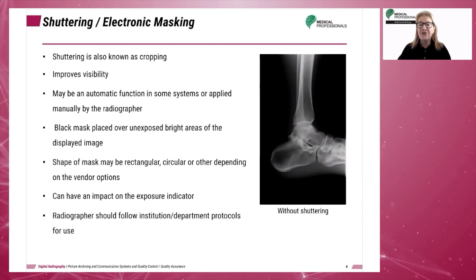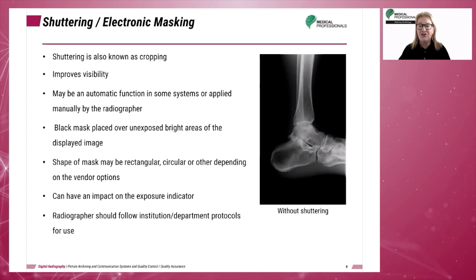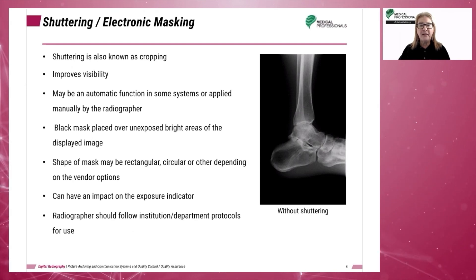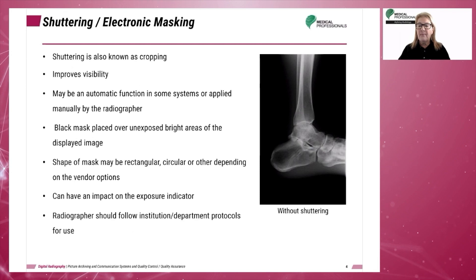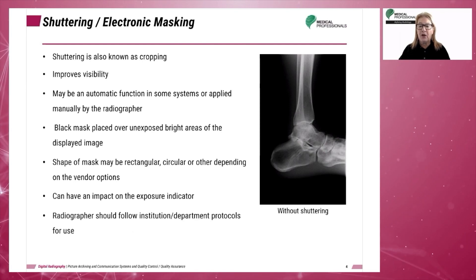Image shuttering allows the radiographer to place a black border or background around the original collimated edges of the image. The black border eliminates any white areas seen around a collimated image. Image shuttering is not to be used as a replacement for actual pre-exposure collimation or beam restriction. Proper collimation restricts the x-ray beam to the anatomy of interest, reduces patient dose, and increases contrast resolution by reducing the amount of scatter produced. Image shuttering simply makes the displayed image more aesthetically pleasing to the viewer, and institutional and departmental protocols should be followed.